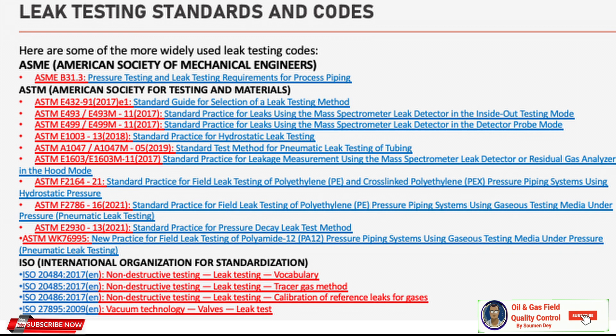If you have a client standard, both should be compared — generally client or local standards refer to these international standards. Some of the ASME society standards include ASME B31.3, which is a very popular standard for process piping, and ASTM standards E432, E493, E499, E1003, A1047, and E1603. Also ASTM F2164, F2786, and E2930. International standards include ISO 20484 for vocabulary, ISO 20485 for tracer gas methods, ISO 20486 for calibration of reference leaks for gases, and ISO 27895 for valve leak testing.